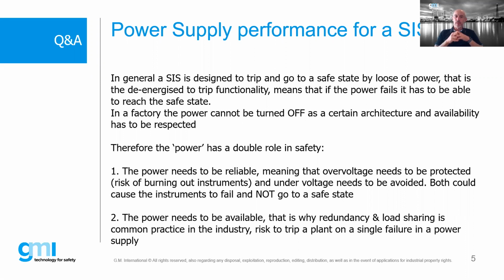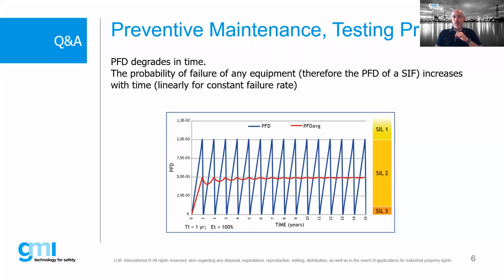Also, the power supply needs to be available and must be redundant, with load sharing being a really common practice used in industries. We also know about preventive maintenance and the proof testing. If you are using a SIL device, this SIL certification is valid for a certain number of years, depending on the hardware and the application. But the probability of dangerous demand degrades in time, so the risk of a failure will be higher over time. The more time, the higher the probability of demand. If you want to return to the initial situation, the hardware must be tested after a certain number of years. This proof test interval is specified in the safety manual supplied by the manufacturer.